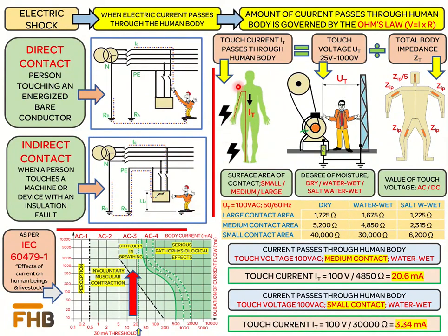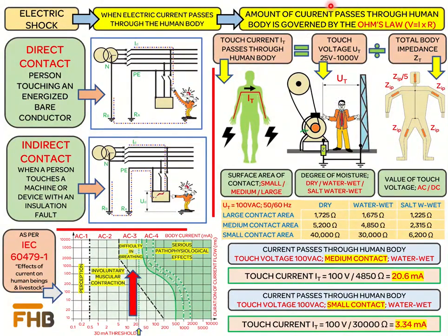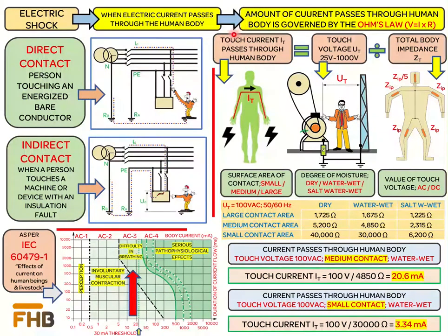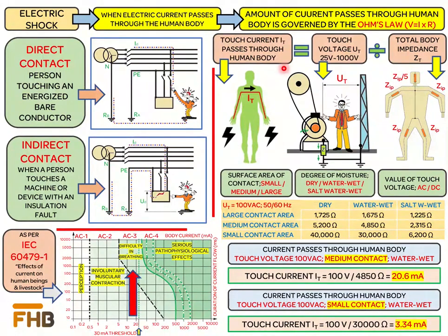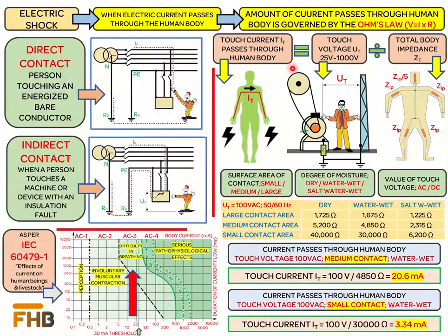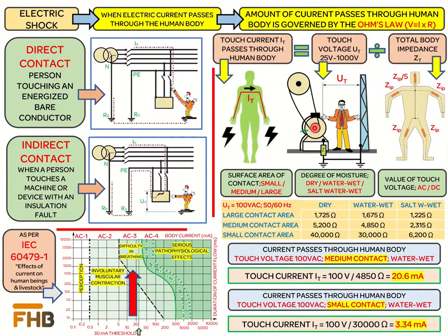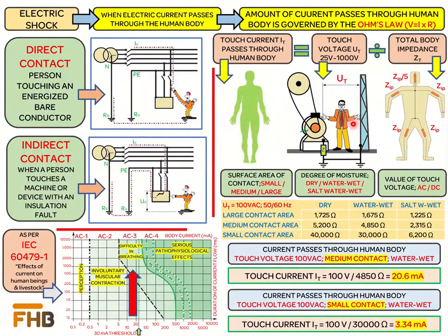The electric current passing through the human body is governed by Ohm's law: voltage equals current times resistance. Our target is to find the magnitude of current passing through the human body, as the danger to a person subjected to an electric shock is mainly dependent on the magnitude and duration of the current flow. For a human body subjected to an electric shock, the voltage is called the touch voltage, which is the voltage between the body part touching the energized object and the part touching the ground, as shown in the picture.